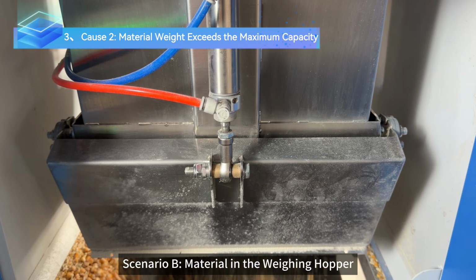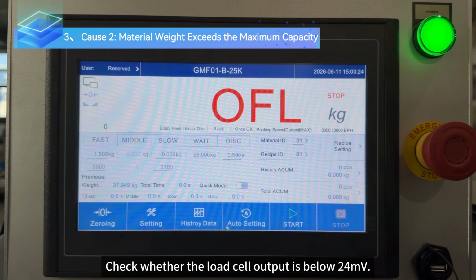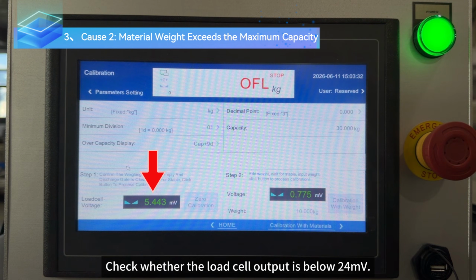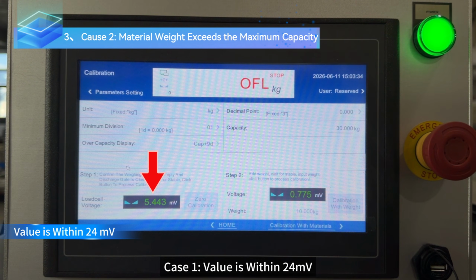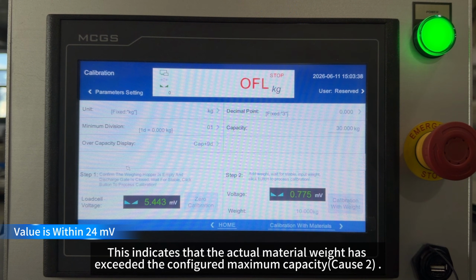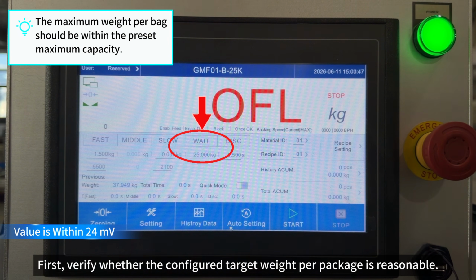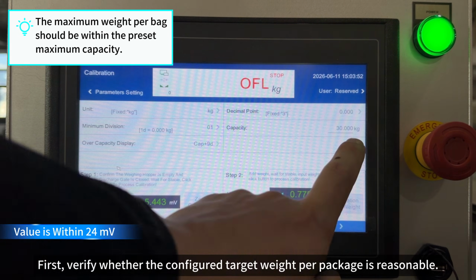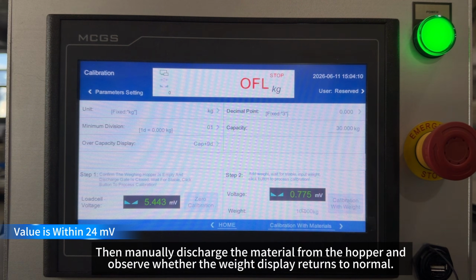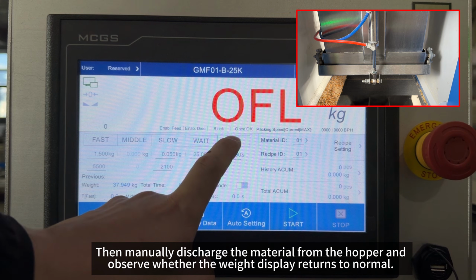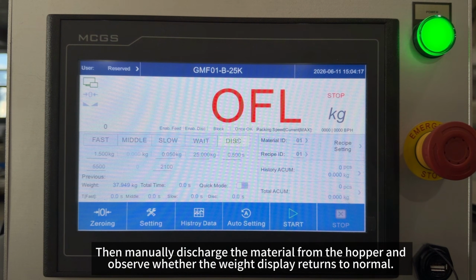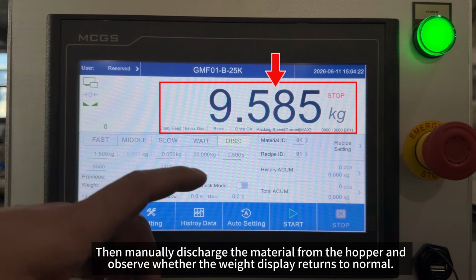Scenario B, material in the weighing hopper. Check whether the load cell output is below 24 mV. Case 1, value is within 24 mV. This indicates that the actual material weight has exceeded the configured maximum capacity. First, verify whether the configured target weight per package is reasonable. Then manually discharge the material from the hopper and observe whether the weight display returns to normal.